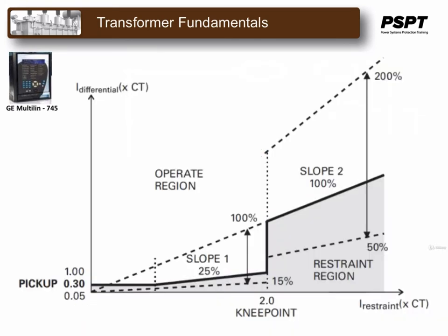The 745 offers percent differential protection and features the equivalent of 3 single-phase differential current relays. Each has dual slope percent differential with second and/or fifth harmonic restraint to protect against maloperation due to magnetizing inrush current during transformer energization and overexcitation. Each differential element has a programmable dual slope percentage restraint with adjustable slope break points.